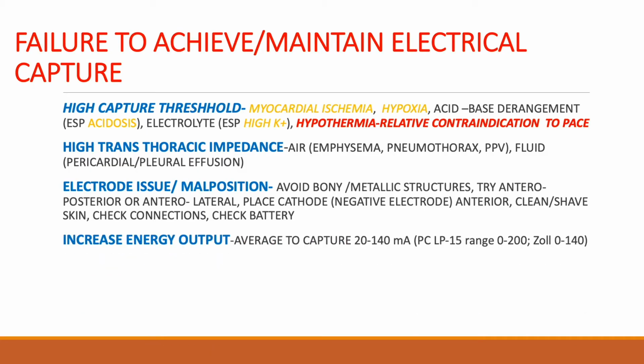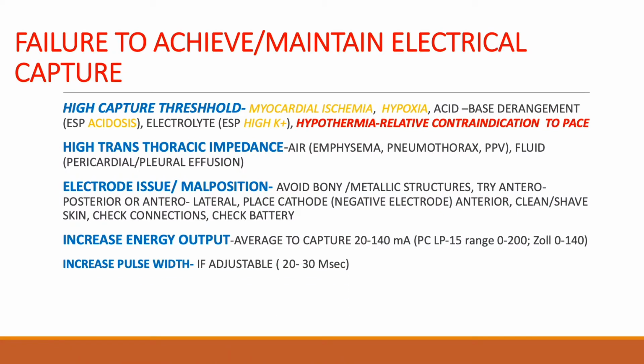One thing you can do, and I'm sure you do this, is increase the energy output. Most people capture with transcutaneous pacing somewhere between 20 and 140 milliamps. If you get above 80 milliamps, that tends to hurt if the patient is conscious. The Physio-Control, I believe, has a range of 0 to 200 milliamps—does anybody know if that's true, or am I lying? I think that's true, okay, you can check that. The Zoll is something similar, 0 to 140, I think. So you can increase the energy until you achieve capture, but if you don't get it at 140 or so, you're probably not going to get it at 200. Forget about that—I'm pretty sure you don't have an adjustable pulse width on this device.